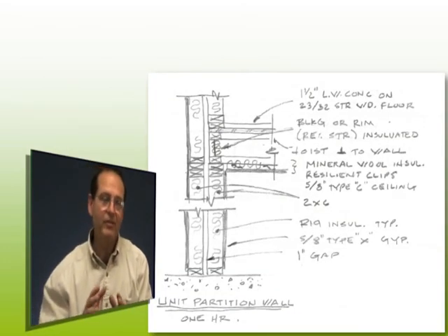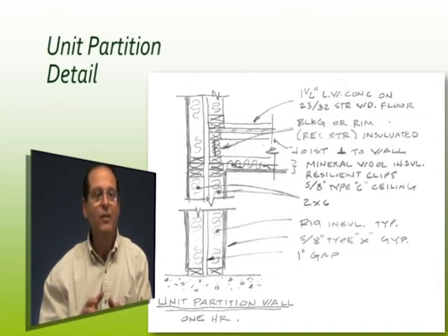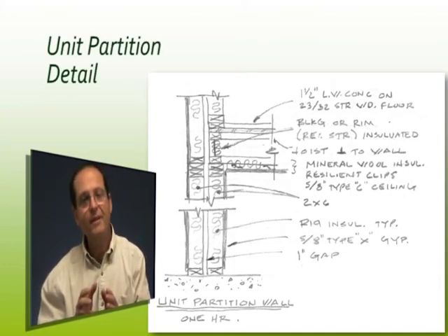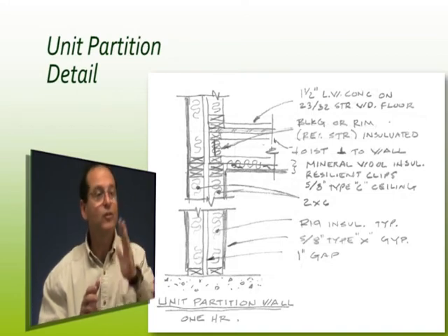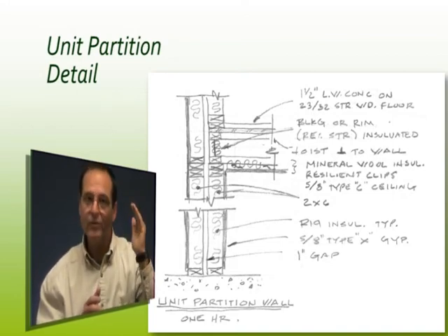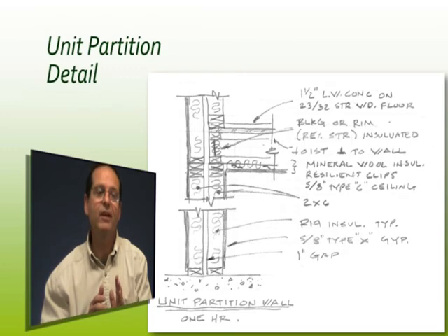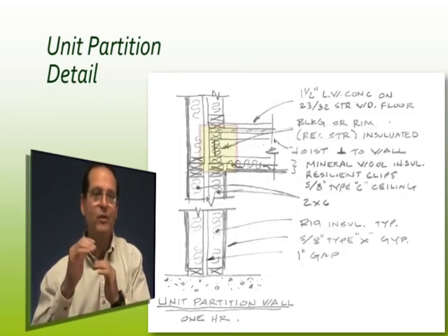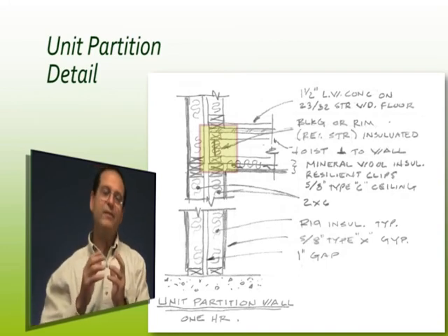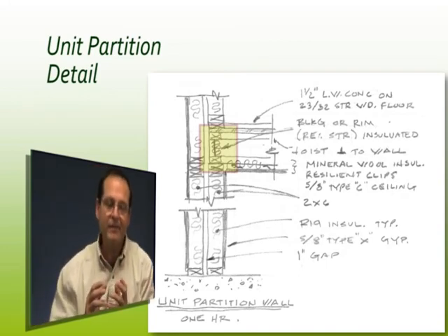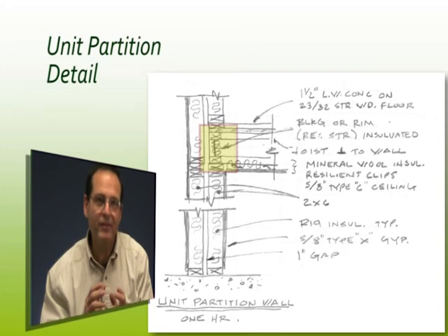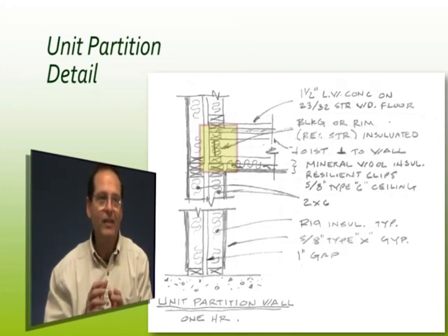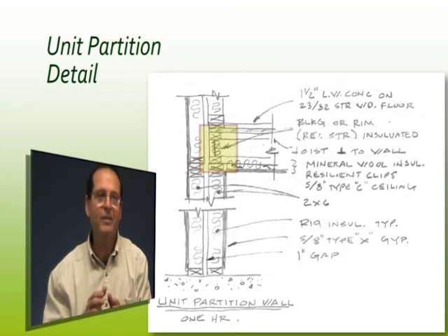The only last piece I want to show you here is the fire wall assembly again. On the left-hand side, this is actually a stairwell opening, so it's 2 floors high. We're just stacking walls on top of the other. No-brainer for that interior wall. The other wall that's in there, notice that the joist sits in it. So this is where things can get a little bit goofy. How you interpret this can vary. You can see the interpretation that this particular architect and building department came up with.